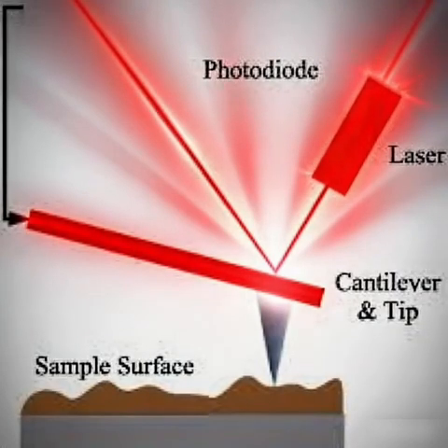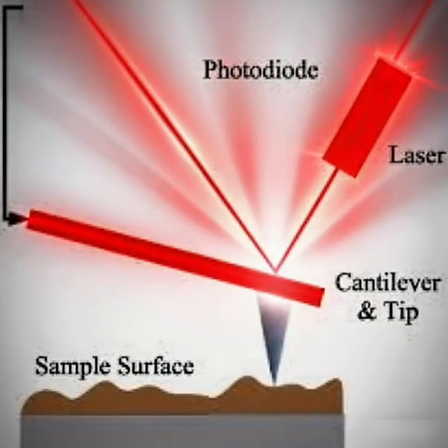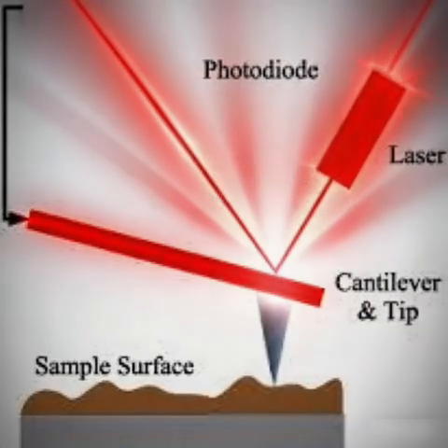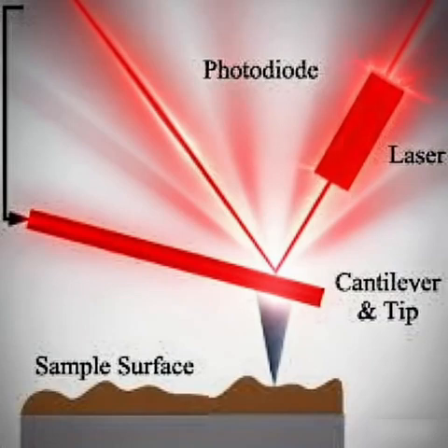Okay, so EFM maps the electrical landscape. What about putting things under pressure? Right. That brings us to nano-TDDB. That stands for time-dependent dielectric breakdown. This is a direct reliability test. It really stresses the material. The idea here is you apply a gradually increasing voltage, a bias, using an AFM conductive probe, and you watch precisely when the insulating layer fails, the breakdown voltage, and how long it takes.